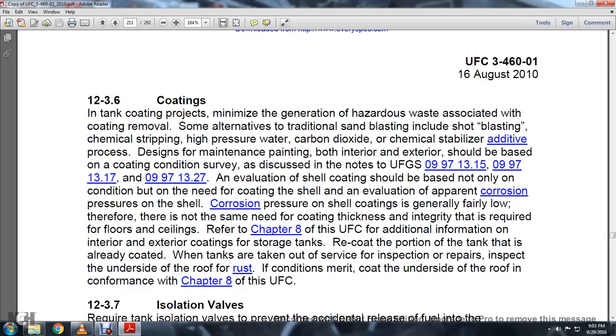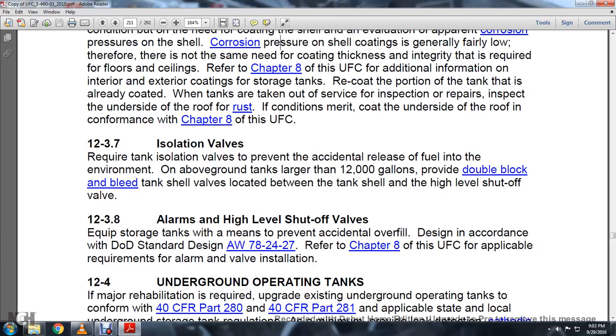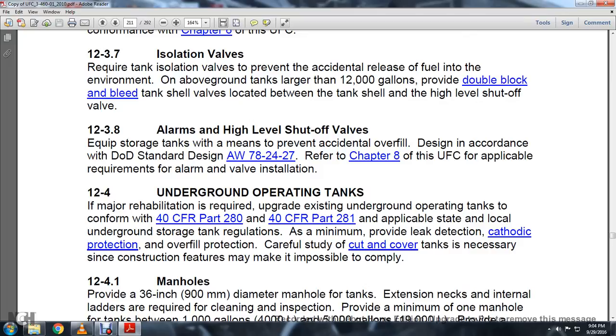Section 12-3-7: Isolation valves. Tanks require isolation valves to prevent accidental release of fuel. Above-ground storage tanks over 12,000 gallons should be provided with double block-and-bleed tank valves located between the tank shell and the high-level shut-off valve. Section 12-3-8: Alarms and high-level shut-off valves. Storage tanks must have equipment to prevent accidental overfilling. Design according to Department of Defense Standards AW78-2427 and Chapter 8 of the UFC for applicable alarm and valve installation requirements.